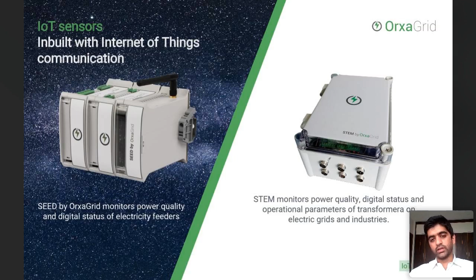The device on the right is very similar to the seed, but the stem device is mainly focused on monitoring assets such as the power transformer. It also monitors power quality features, digital inputs and statuses such as fans and pumps, and measures operational parameters like transformer temperature, oil level, and so on. The device comes in an IP67 box, so it's ruggedized for outdoor installations, and it's an end-to-end asset monitoring unit.